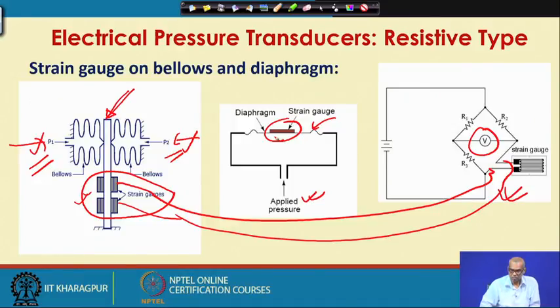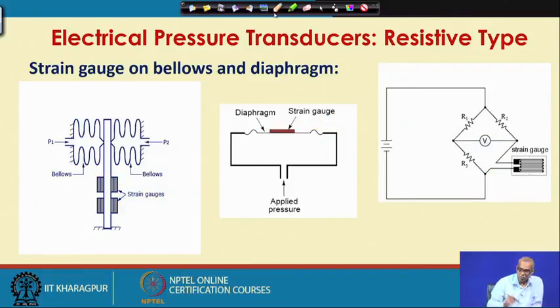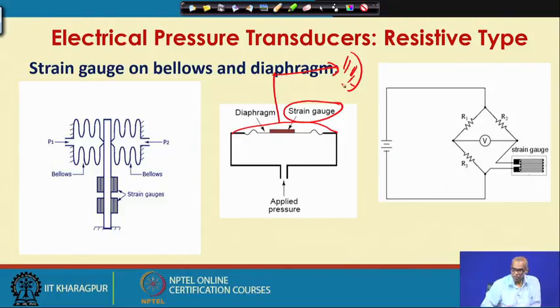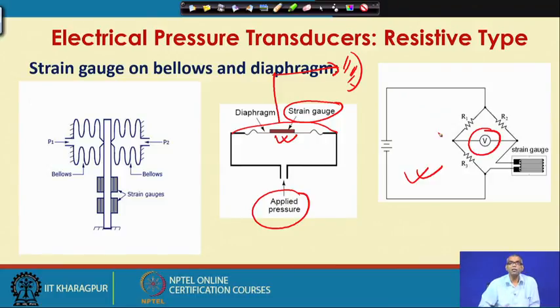So, there will be a change in resistance in the strain gauge wire, which can be read using the Wheatstone bridge principle. So, here also we convert this diaphragm gauge to an electrical pressure transducer. Note, if you do not use this strain gauge, you will perhaps read the deflection by attaching a pointer and scale to this diaphragm. But if you put a strain gauge on the diaphragm, you can measure the change in resistance due to application of pressure by using the Wheatstone bridge principle, and you will get an electrical signal voltage as output, which becomes more convenient for measurement purpose.